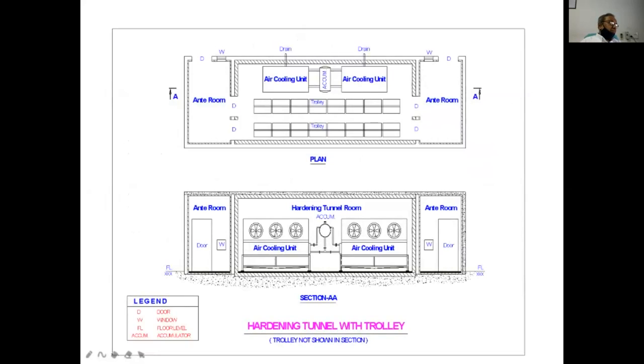How does it look? This is a simple air blast freezer where you can see there is an air cooling unit that will give very cold air, minus 25, minus 30 degrees, and the ice cream is kept in the trolley here. This is one side where ice cream enters and the second side where it is taken out, and this requires a retention time for the ice cream. It is not a continuous process. It requires a certain retention time.